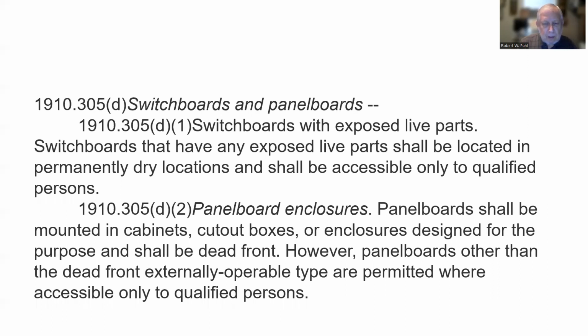Switchboards and panel boards. Again, this is more like panel boards. Panel boards shall be mounted in cabinets, cutout boxes, or enclosures designed for the purpose and shall be dead front. Dead front means there's nothing you can touch on there that's going to hurt you. However, panel boards other than the dead front, externally operable types are permitted where accessible only to qualified persons.